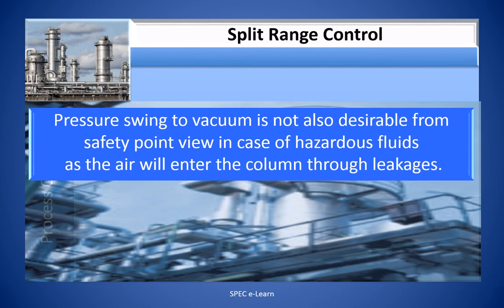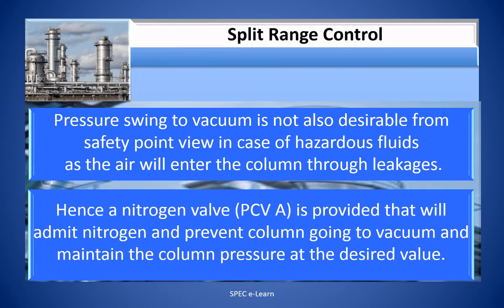Pressure swing to vacuum is not desirable from a safety point of view in case of hazardous fluids, as air will enter the column through leakages. Hence, nitrogen valve PCVA is provided to admit nitrogen and prevent the column from going into vacuum, maintaining the column pressure at the desired value.